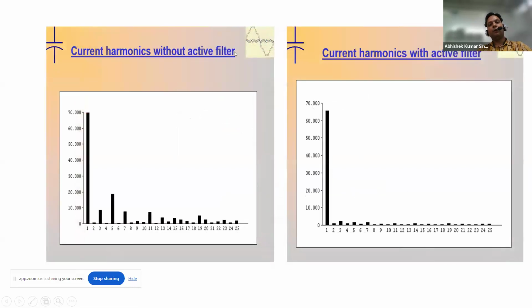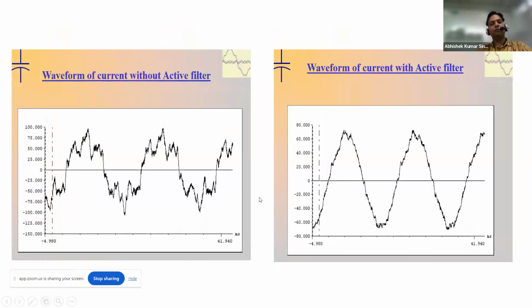Now, current harmonics without an active filter, as we've seen. There are multiple, you may say the fifth harmonic, seventh harmonic, 11th harmonic. And then after applying the active filter, all are almost nullified. This is the same waveform. This is a very much distorted waveform, but after placing the active filter, the waveform is almost sinusoidal, because this is basically our primary, the main goal, to make the waveform sinusoidal, so that the system will run efficiently and we can reduce the losses from the system.